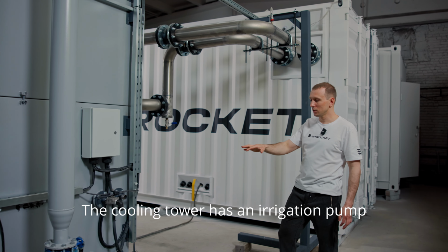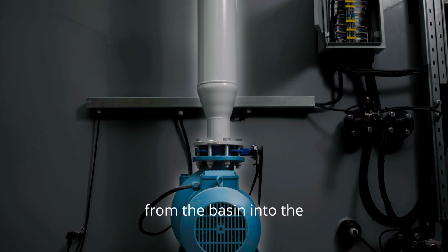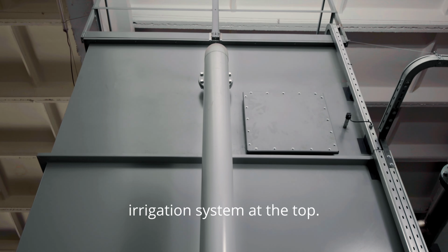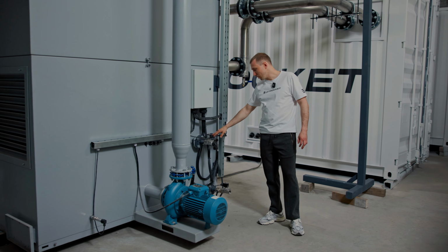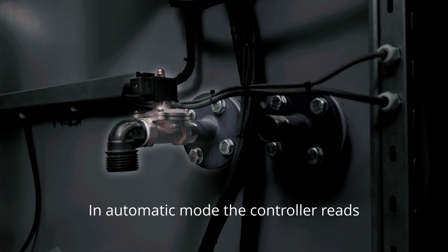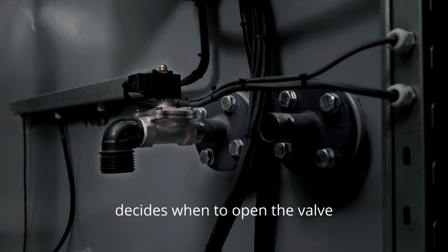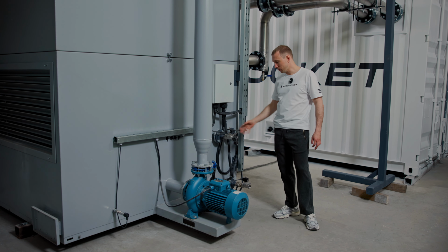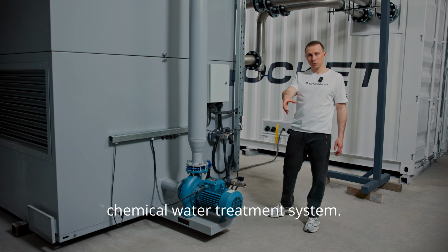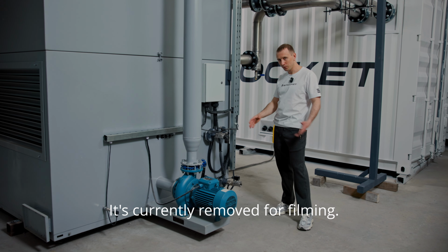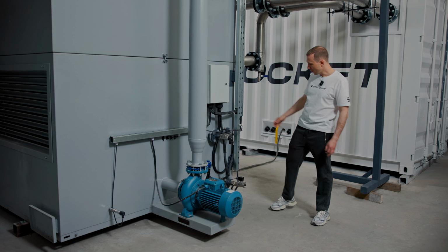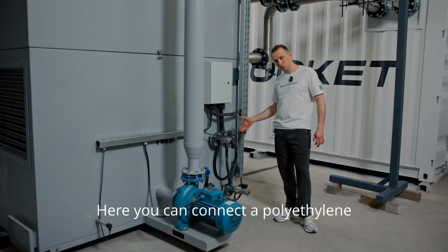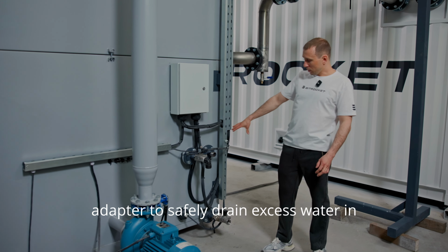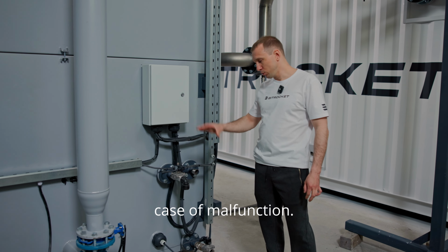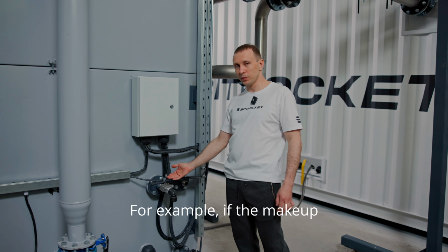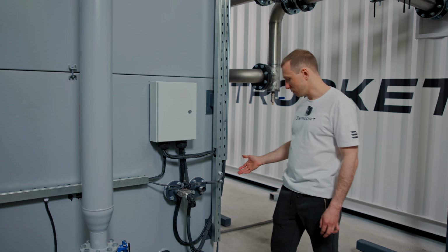The cooling tower has an irrigation pump, which delivers water from the basin into the irrigation system at the top. The makeup valve. In automatic mode, the controller reads level sensor data and decides when to open the valve for water replenishment. The water passes through a chemical water treatment system. It's currently removed for filming. Overflow system. Here you can connect a polyethylene adapter to safely drain excess water in case of malfunction. For example, if the makeup valve keeps filling the system.